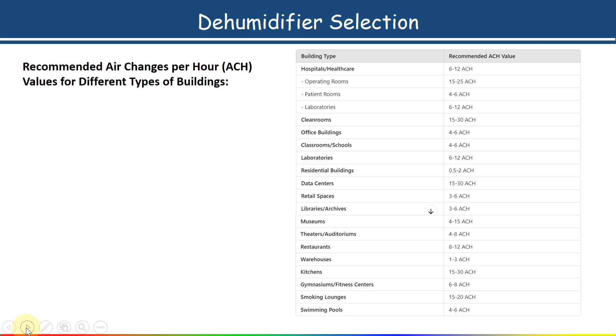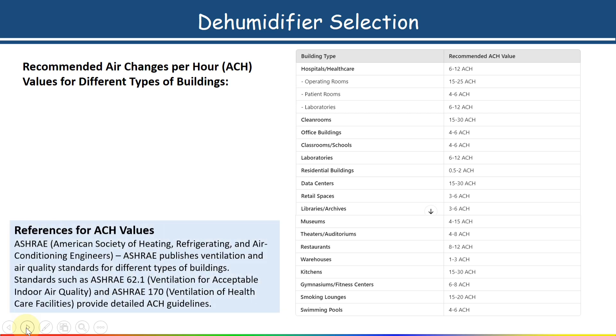The reference for ACH values is ASHRAE published ventilation and air quality standards for different types of buildings — specifically ASHRAE 62.1, the ventilation standard for acceptable indoor air quality, and ASHRAE 170, the ventilation standard for healthcare facilities, which provide detailed ACH guidelines. Some of these are shown in this table. So: first, calculate the room volume; second, determine the ACH value from the table or from these standards.